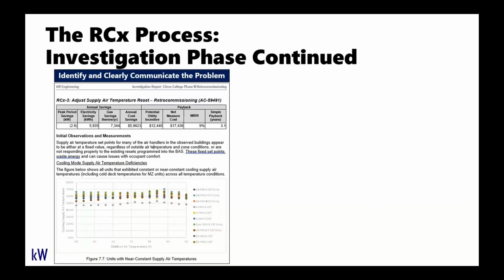Here's a snippet of one measure from our phase 3 report with Citrus. This was a measure to adjust the supply air temperature control for the air handlers of a subset of their buildings. The air temperature had been fixed before, and we were recommending a supply air temperature reset, which some of you may have heard of before. Our goal here is to identify and clearly communicate the problem to Fred and the other building operators who are making these decisions, as well as communicate the potential savings, costs, and cost effectiveness of that measure.